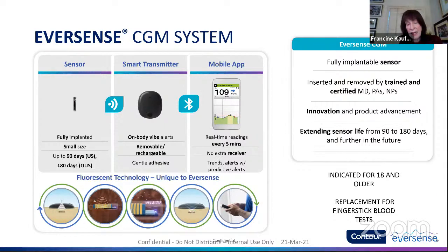The transmitter puts energy into the sensor through a near field energy source and powers the sensor, so the transmitter has to be on for the sensor to be active and working. The transmitter sends down energy that excites some LEDs in the sensor itself. Those LEDs light up the sensing surface, which can pick up the reversible binding of glucose. This happens every 5 minutes—glucose attaches, unattaches, more glucose reattaches—allowing it to measure the interstitial glucose concentration.